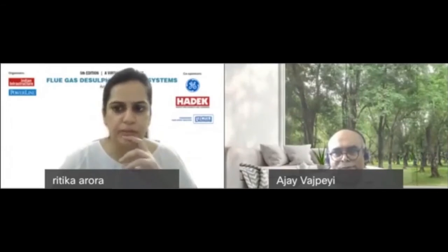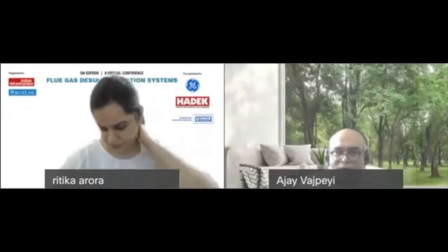How do you control the outfall seawater temperature from the absorber in a seawater FGD plant? In seawater FGD plants, you many times have cooling channels which cool down the seawater going out from the FGD. Apart from that, you also do a certain amount of dilution so that you can control the outfall seawater temperature.